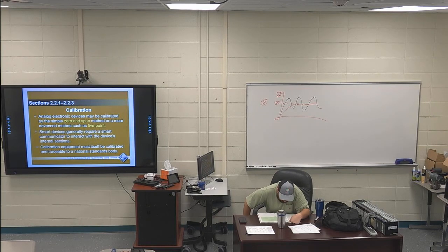Next paragraph, first. Dude, it's insane. The first 3 sentences of that next paragraph are highlighted. Instrument asset management systems are software packages that run on a network computer or server. They communicate with smart instruments and keep detailed records automatically using rules established by plant personnel. They can schedule calibrations, alert technicians of impending failures, and help keep track of everything without the need to do so on paper.